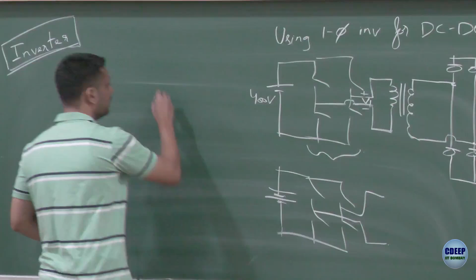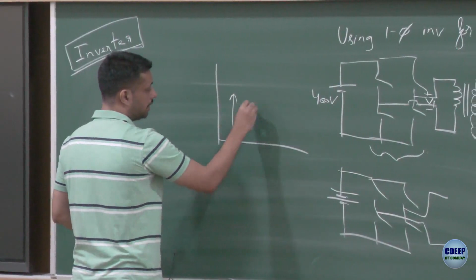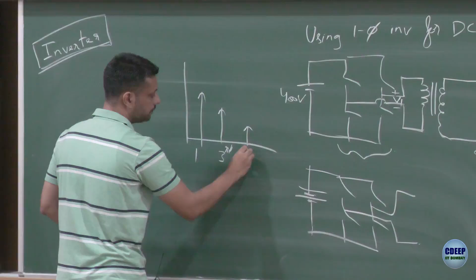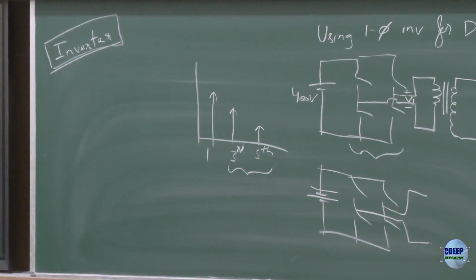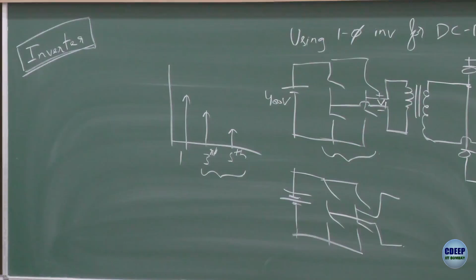If you use fundamental modulation, you get a fundamental component at 50 hertz, plus a third harmonic and a fifth harmonic component. These go into the fan as low, audible frequencies, so you hear the third, fifth, seventh harmonics causing vibrations. That happens with fundamental modulation.